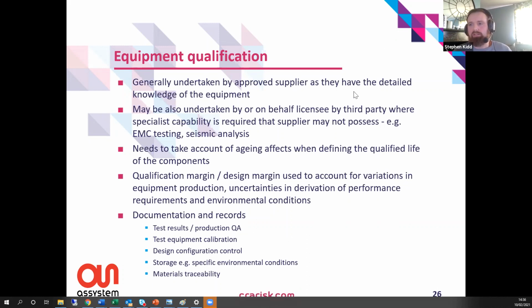I mentioned already there's a defined qualified life for components, and that needs to take account of aging effects. So it's not just qualifying at the start and then that's it. We need to be able to confidently say that it will retain an adequate level of performance all the way through its qualified life. And that's where we want to build in qualification or design margin. That takes account of any potential uncertainties in the definition of the environmental conditions that it needs to operate in, or the original requirements from the safety case, and also any variations in the production output. So there may be slight variations in the quality of items that come out of the production line.